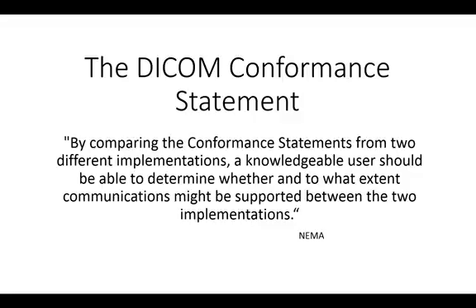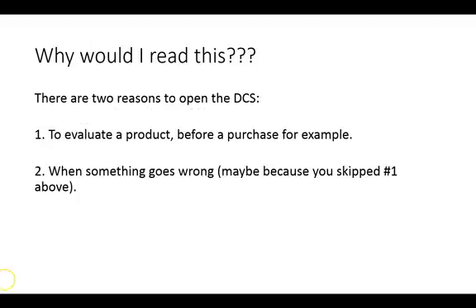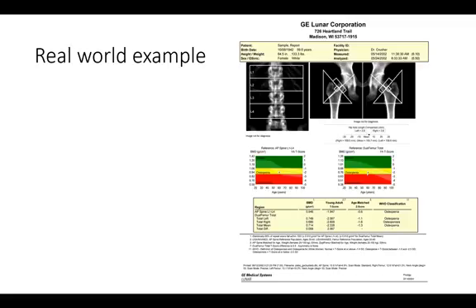Let's talk about the DICOM conformance statement. The DICOM conformance statement will tell you how an application entity will communicate with other AEs on your DICOM network. DICOM conformance statements are typically 300 pages long and full of complex DICOM terms. Sometimes other departments will purchase a DICOM device without consulting you.